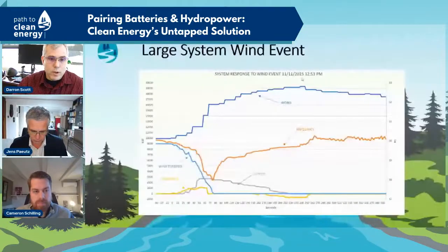The battery energy storage system plays a very key role in how our whole system works together. Being an isolated grid, our battery system is set up in a total droop control mode, and it's there for the low frequency side. Our hydro system controls the high frequency side, and the wind turbines just do whatever they want to do because it's very difficult to control them in a lot of ways. I did supply some information on a graph that might help explain how our system comes together.